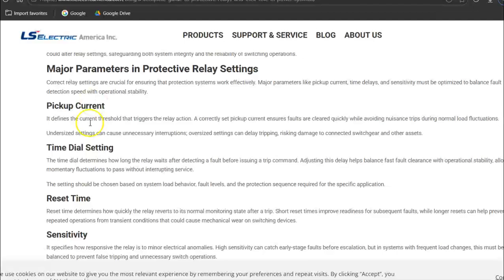So what do we get when you're doing Lab 11? Pickup current is basically the tripping point. That is 100% full load current. You set it. Now you can set it in a variety of ways for your system. Every system is going to have a different setting. So once your current goes above the pickup current, it's in the fault zone. Then your timed contacts will start to count. And the higher it goes, hopefully the current will go back down again, and then it never actually trips. But if the current goes really high, then the instantaneous trip will go.